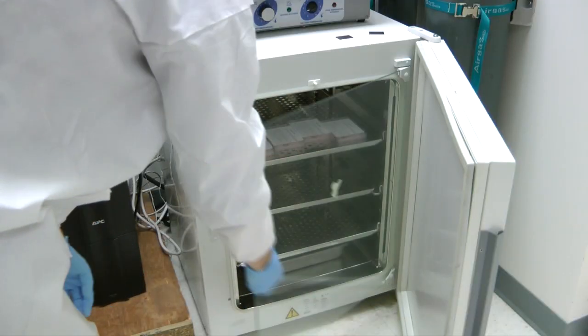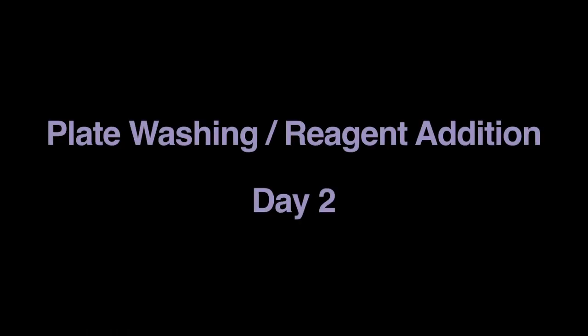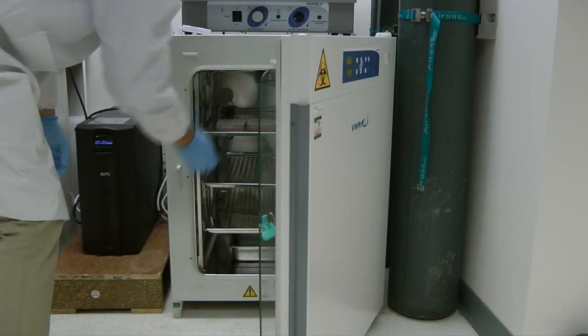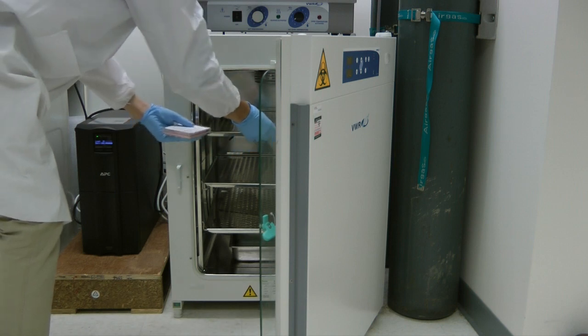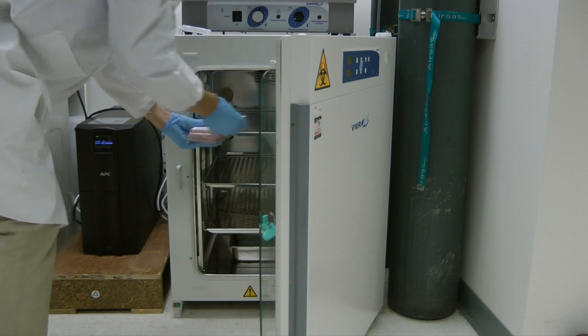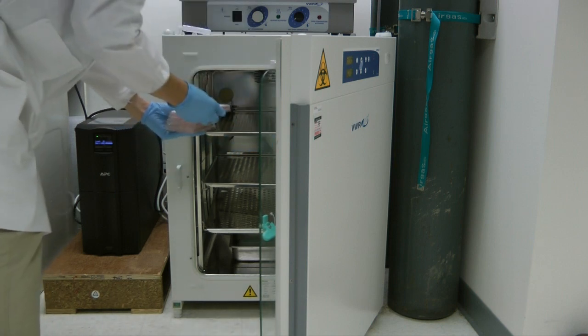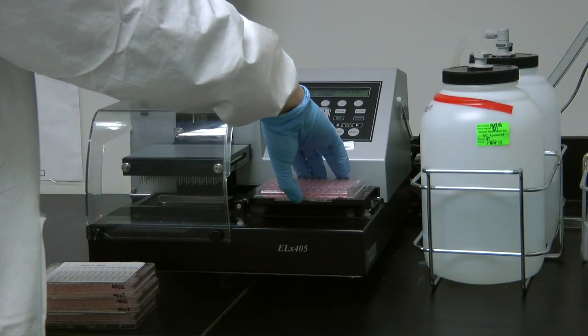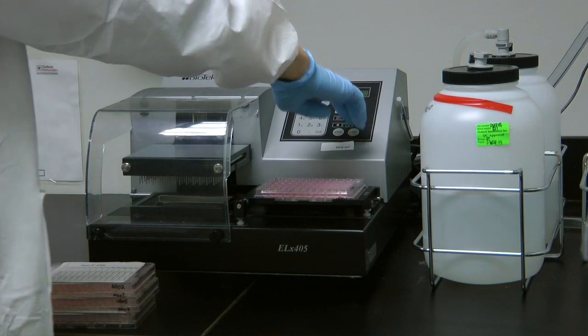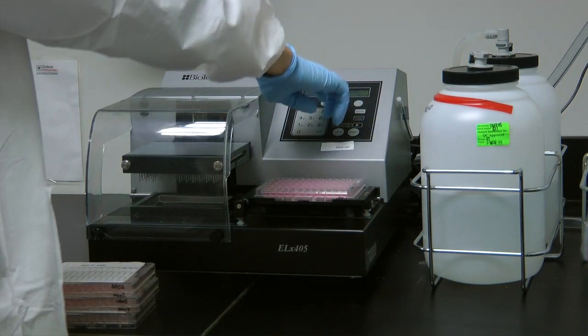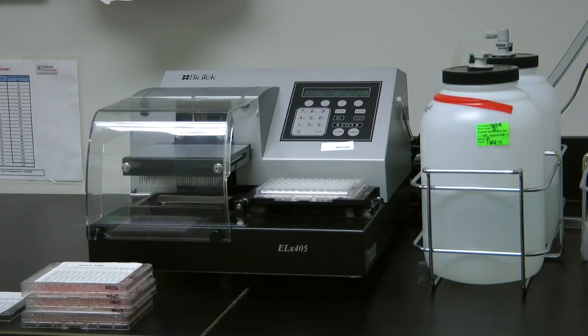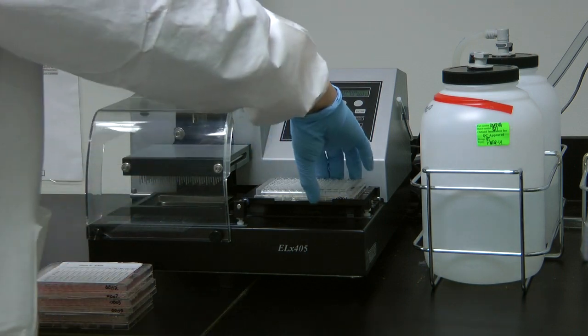Plates are then incubated overnight. The Janus liquid handling system is also used on day 2 to develop spots and prepare the plates for reading. Following incubation, the T-spot TB microtiter plates are washed with phosphate-buffered saline. This step can be performed on the Janus or a plate washer. Wash cycle times can be shortened to 30 seconds with a plate washer such as the Biotek ELx405. Four plates can be washed in less than three minutes.